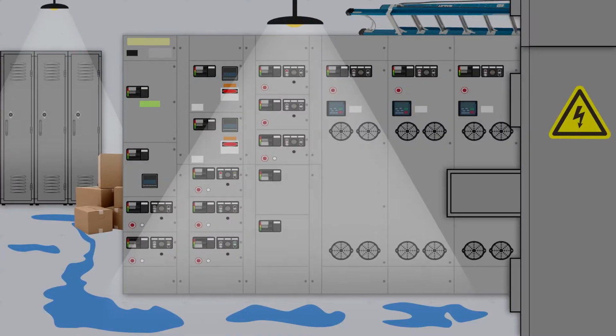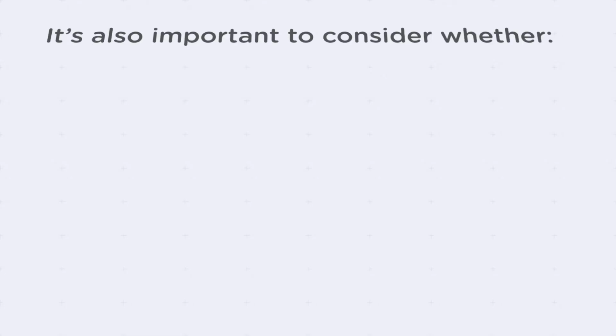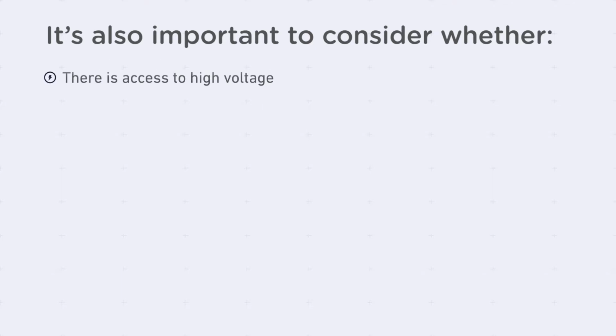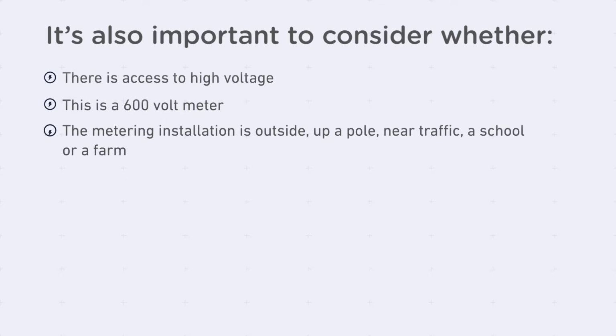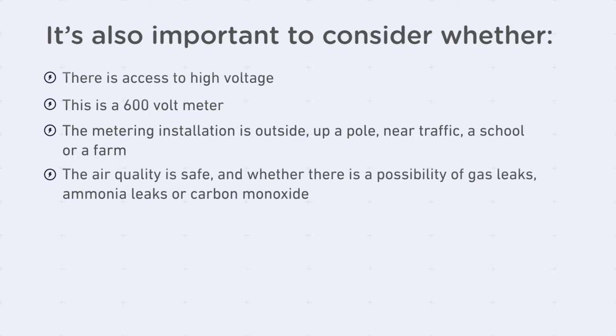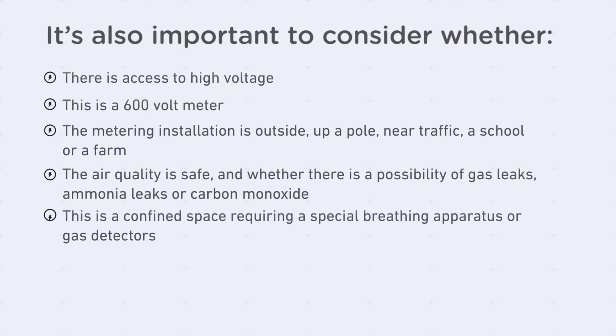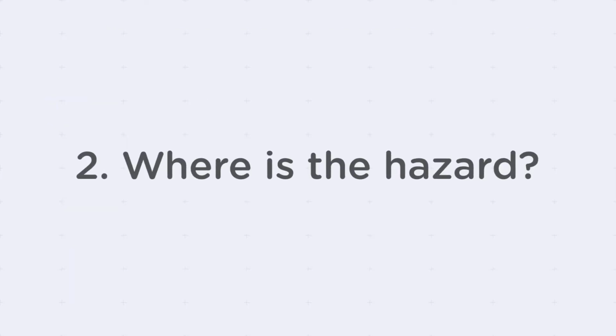Some examples of hazards to look for are water on the floor around metering or electrical equipment, poor lighting in an electrical room, limited space because the room is used as storage, potential for falling debris when cabinet doors are opened, and other moving machinery or equipment. It's also important to consider whether there is access to high voltage. Is this a 600-volt meter? Is the metering installation outside, up a pole, near traffic, a school, or a farm? Is the air quality safe, and is there a possibility of gas leaks, ammonia leaks, or carbon monoxide? Is this a confined space requiring a special breathing apparatus or gas detectors, in which case an inspector is not qualified to enter?